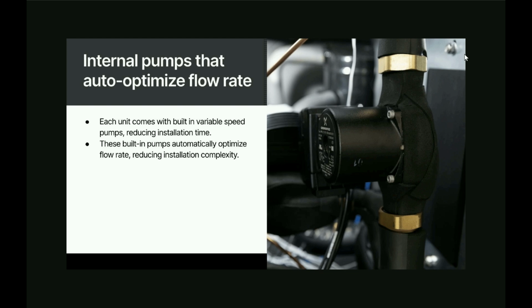So one of the other labor-intensive parts of installing a heat pump is getting the pumps together and getting everything integrated and setting the flow. So we just built them in. We got variable speed ground loop pumps included in there, and then they automatically adjust the flow rate. So it saves guys a little bit of time.